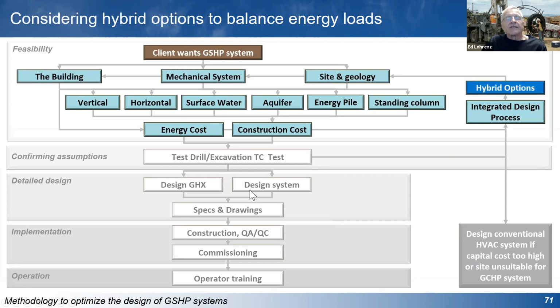And then if all else fails, if you can't balance the loads within the mechanical system design or the building design, and there are certain places you simply can't do that, then you might want to look at a hybrid option. It might be a fluid cooler or some other way of getting rid of excess heat, or adding a fossil fuel boiler or some other kind of boiler, electric boiler or whatever, to provide excess heat when it's needed. And there's a number of different strategies that can be used to dump excess heat into the ground.